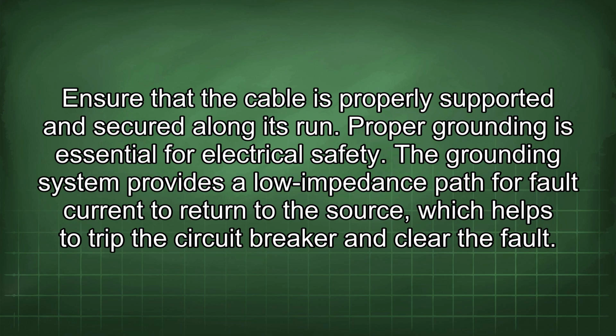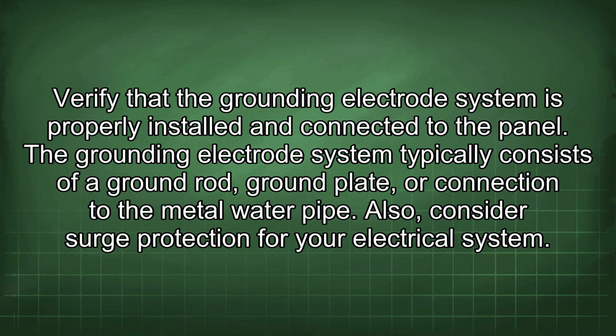Proper grounding is essential for electrical safety. The grounding system provides a low impedance path for fault current to return to the source, which helps to trip the circuit breaker and clear the fault. Verify that the grounding electrode system is properly installed and connected to the panel. The grounding electrode system typically consists of a ground rod, ground plate, or connection to the metal water pipe.